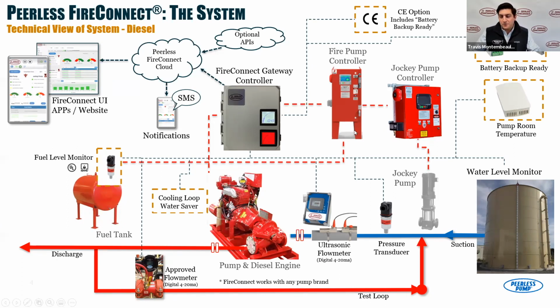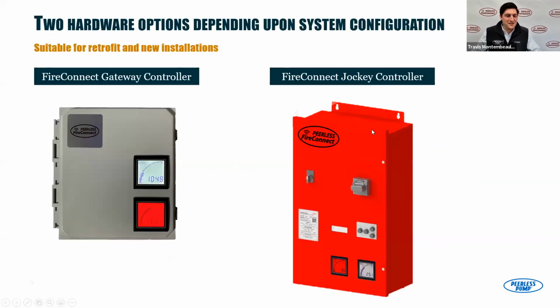Not every fire pump controller is Modbus enabled, especially jockey pump controllers. They are typically fairly basic in nature. So a lot of times those would need to be replaced or retrofit. So that's a consideration so that we can get that data out. But we'll talk to you just in a moment about some different opportunities that you may have here.